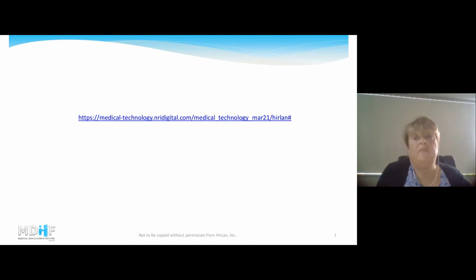However, on the other hand, you may find use errors that have not been found in the original use-related risk analysis, and when evaluated, tend to be very high. You have to put in a mitigation, and then yes, you have to reevaluate if that mitigation is effective. So understand, you don't pass or fail a human factors test. What you do is you have to demonstrate that the use-related risk has been reduced as far as possible, and that this device is going to be safe by the intended users in the intended environment for the intended purpose.